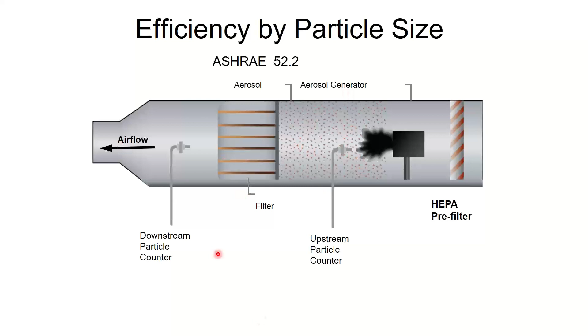It said the minimum MERV rating you need to be able to catch COVID is a MERV 14, but if you can't handle that pressure drop, put in at least a MERV 13, right? And like, well, which one catches it? What the hell, right? Well, MERV 13 will catch some of it. If you remember, I said this test doesn't catch everything, right? It catches most of those particles, and you need to catch a certain amount to get the qualification. And COVID is like right between the MERV 13 and MERV 14 number.